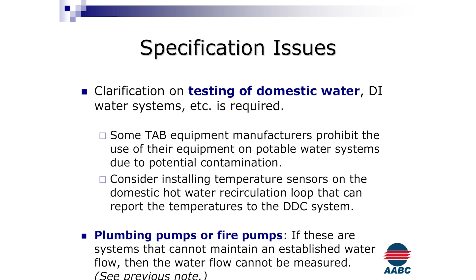Consider installing temperature sensors on the domestic hot water recirc loop that can report back to the DDC system. Energy, right? This is why we're here. One of the biggest losses in energy is heating up water and either it not being used, or it sitting, and we need to watch what's going on in the recirc loop. That will allow us to really tune in how much energy we're putting in to keep a certain temperature, or even analyze what temperature would be appropriate. A lot of places have really high temperature water coming out, and in my experience, sometimes we could lower that down a couple of degrees and maybe eke out a little more savings.